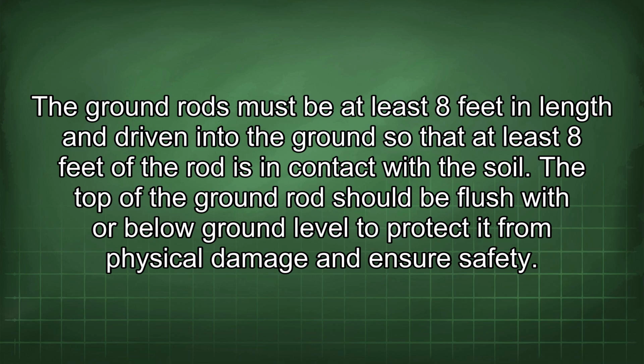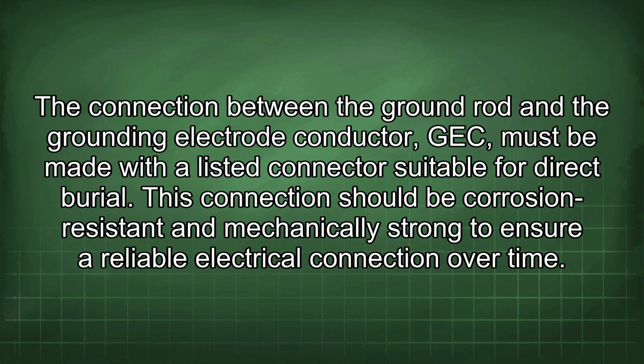and ensure safety. The connection between the ground rod and the grounding electrode conductor, GEC, must be made with a listed connector suitable for direct burial. This connection should be corrosion resistant and mechanically strong to ensure a reliable electrical connection over time.